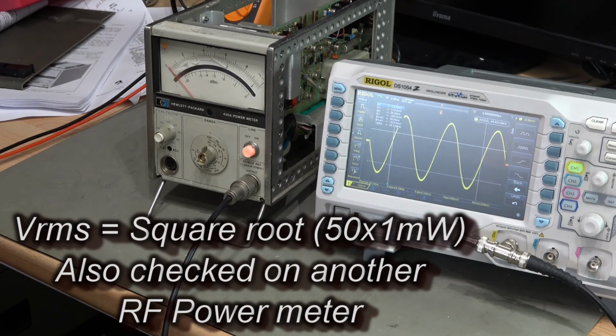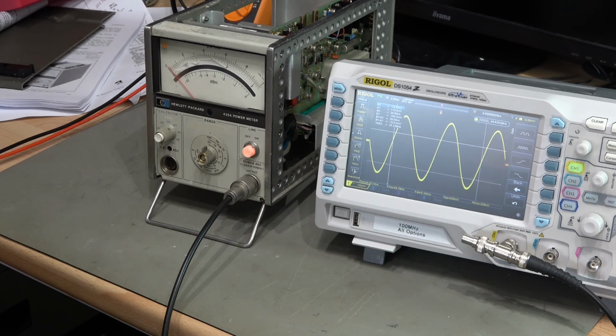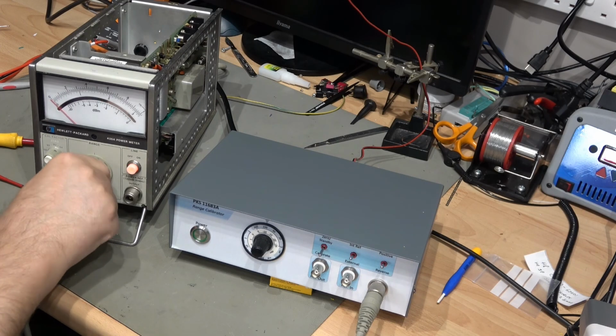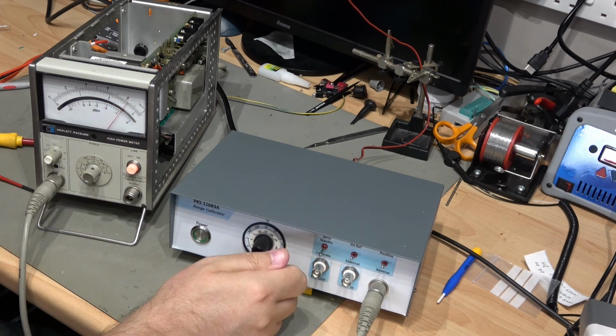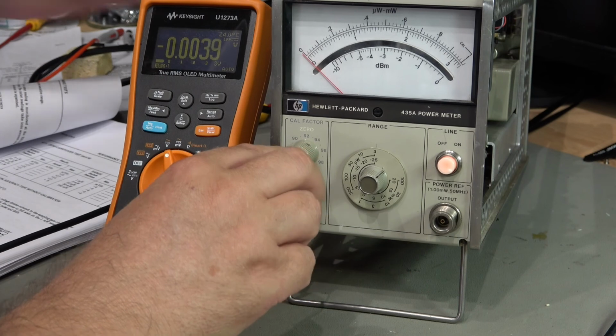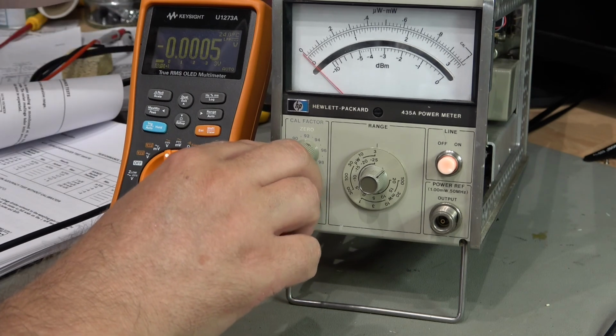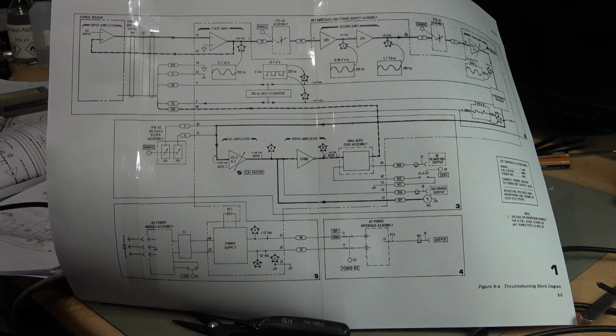So the process then really is seeing what else is wrong. Well, a couple of things were wrong. One is that some of the ranges were over-reading and under-reading, and the second was that the zeroing wasn't working quite right.